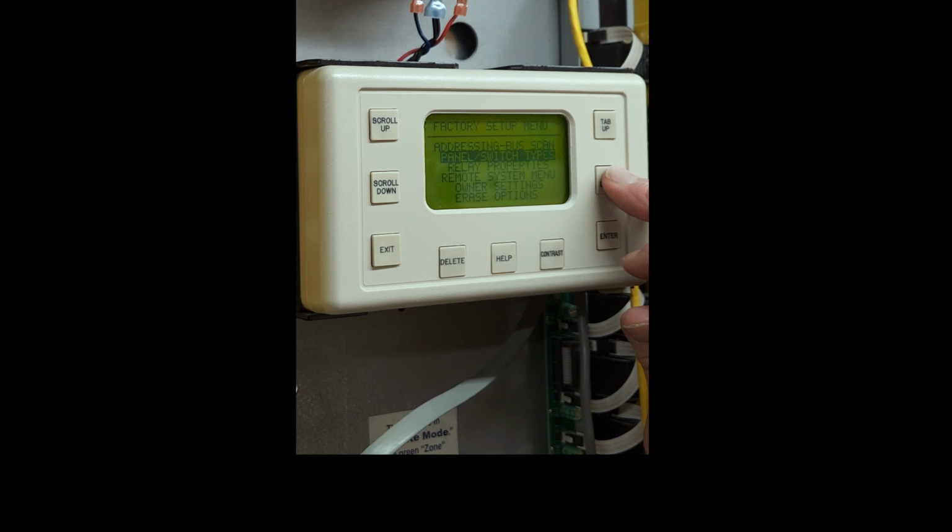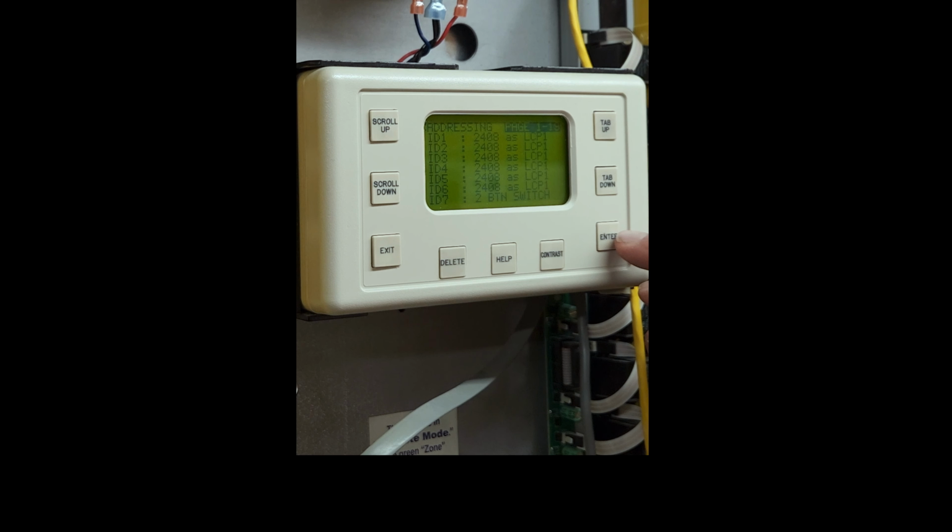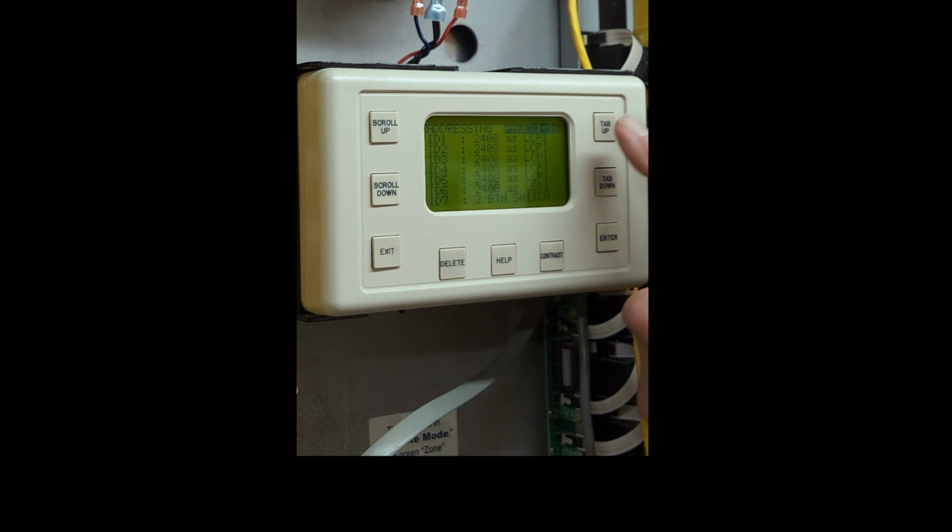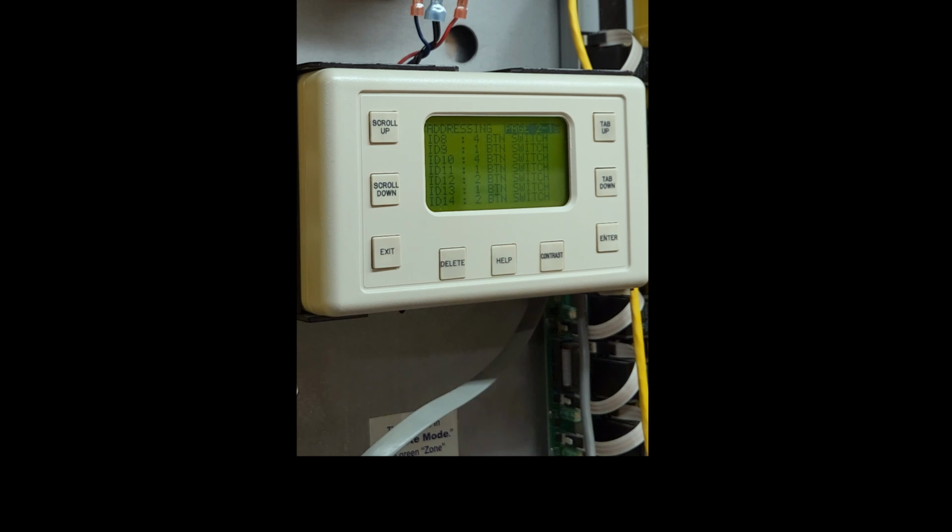Here it shows what you're supposed to have, not what is connected, but what's supposed to. Hit enter. See, ID number 1 through 6 are reserved for this panel because it has 48 relays. Okay. ID number 7 is a 2-button switch. So push a scroll up to go to page 2 of 19. Okay. See, all of those numbers, 8, 9, 10, 11, 12, 13, 14, are all switches.